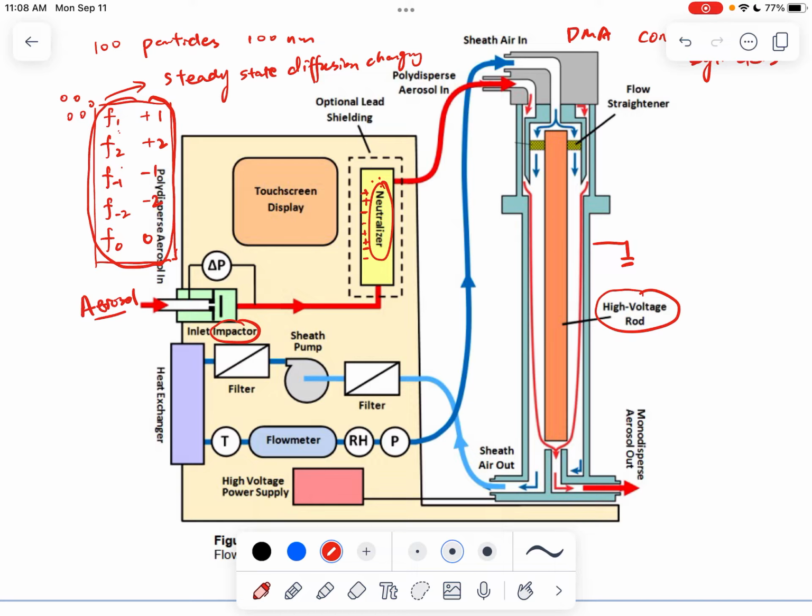So the aerosols are being introduced into, let's say, the upstream of the DMA, and then it's going to get redistributed through this structure here. It may look like it's entering from the left side or the right side, but actually the flow is distributed through an inlet ring. On the inlet ring, there are multiple inlets, where you can introduce the aerosols more uniformly.